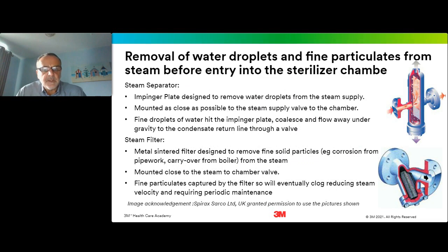And similarly, we can use engineering solutions to remove fine water droplets. This is a small impinger system, and I thank Spirax Sarco for allowing me to use these pictures. The idea here is that as the steam enters the device, it will hit a vertically mounted plate, and as it impinges on the plate, water droplets will collect on the plate and flow away. So it's an effective way of drying the steam and removing liquid water from the steam.